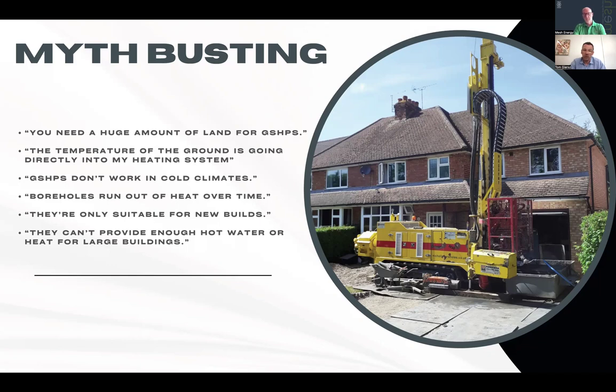We've had experience with lots of systems where boreholes or horizontal collectors were undersized, and then heat pumps are not performing and they are using a lot of electric, and clients are saying, I would like to rip it out because it's costing me too much to run, and it's the heat pump's fault. It's not the heat pump's fault that it's not running well.